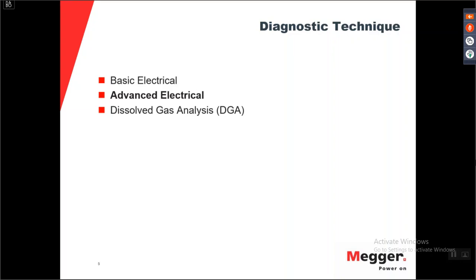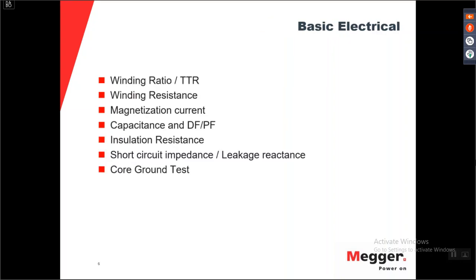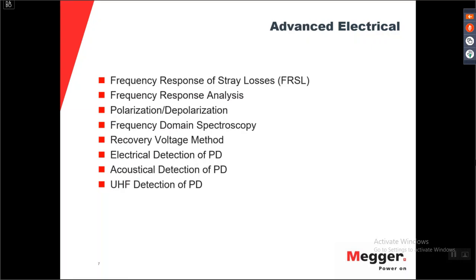And as this is a small recap, the basic electrical tests are the winding ratio or turns ratio, winding resistance, magnetization current or excitation current. It's the same test, different name. Capacitance, dissipation factor, power factor, or tan delta test. Insulation resistance, short circuit impedance or leakage reactance. And then you also have the last one, which is the core ground test. Those were the basic electrical tests that we discussed in part 1. Today, it's the advanced electrical tests.